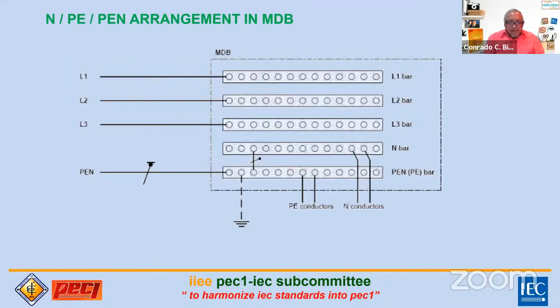Because later things might get mixed up, right? If your PEN ends up on the N bar, that's not allowed. If the N is cut or removed, this jumper, the PEN jumper, you lose protection. So it's a priority to connect it to the PEN bar. This PEN bar can be directly fixed to the frames, no need for an insulator on that bus bar, directly fixed to the frames of the low voltage switchgear or distribution boards. Just make sure that when it's fixed to the frame, it's properly fixed with special or certain types of bolts that ensure continuity with the body. That's why it's handled very carefully.